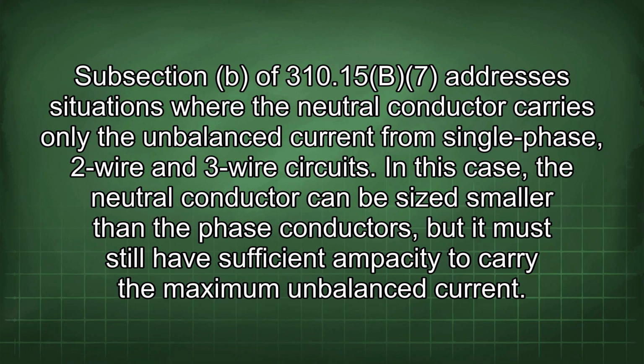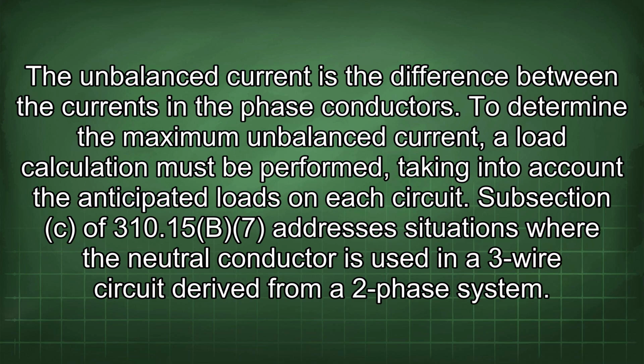Subsection B of 310.15(B)(7) addresses situations where the neutral conductor carries only the unbalanced current from single-phase 2-wire and 3-wire circuits. In this case, the neutral conductor can be sized smaller than the phase conductors, but it must still have sufficient ampacity to carry the maximum unbalanced current. The unbalanced current is the difference between the currents in the phase conductors. To determine the maximum unbalanced current, a load calculation must be performed, taking into account the anticipated loads on each circuit.